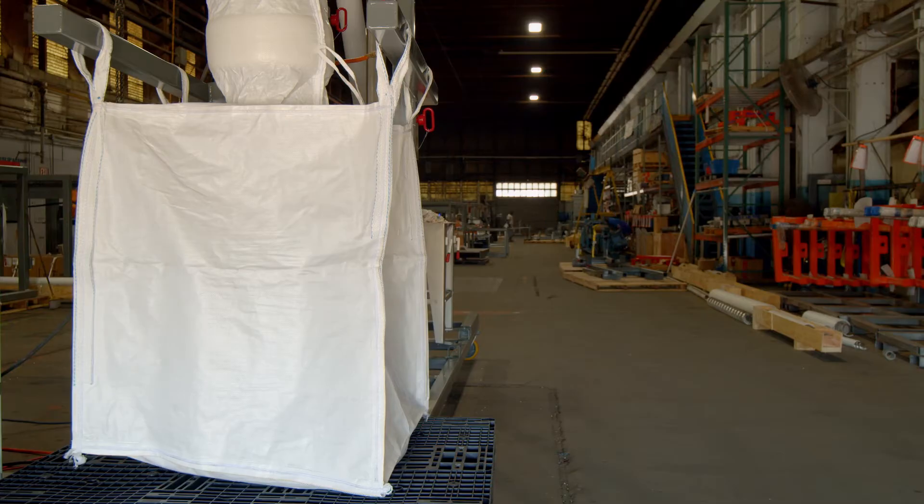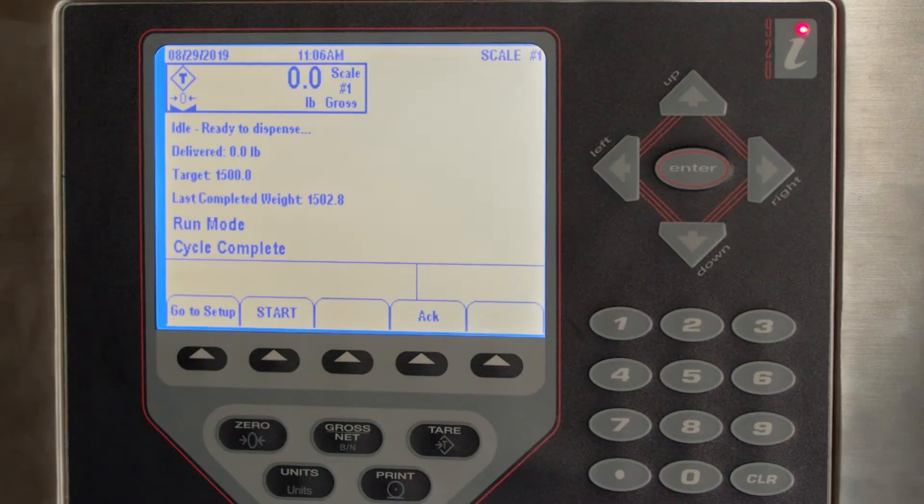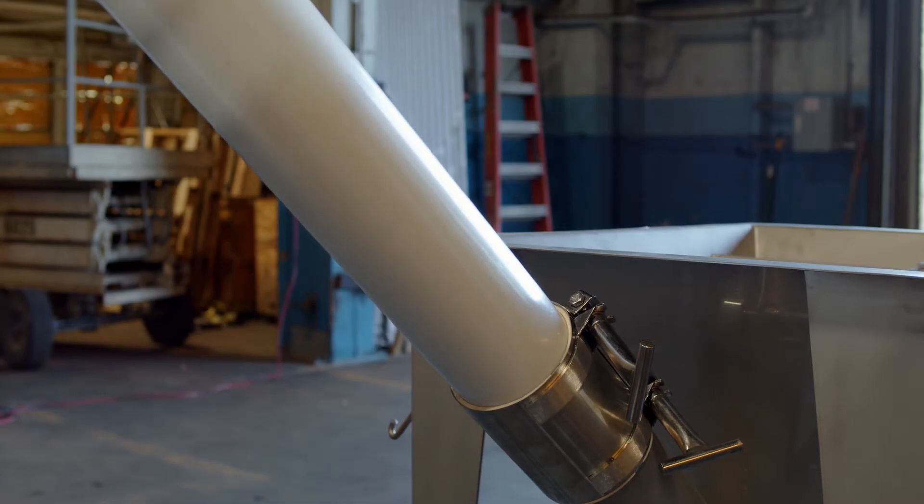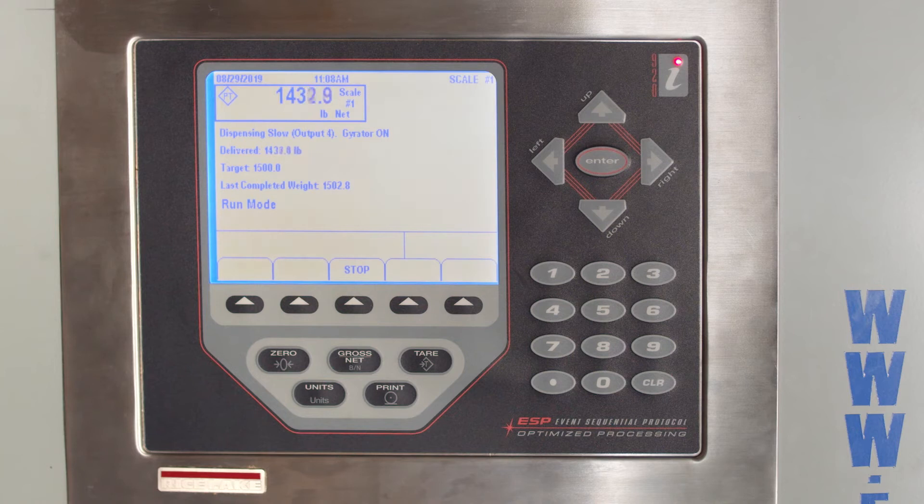The system is a gain in weight, gross weight system. The scale tares to zero, then a signal opens a valve or starts a conveyor in bulk mode.